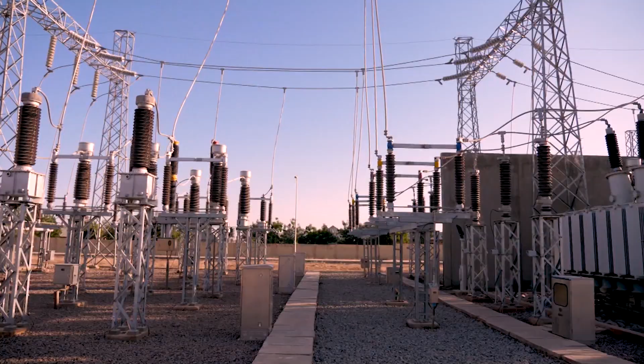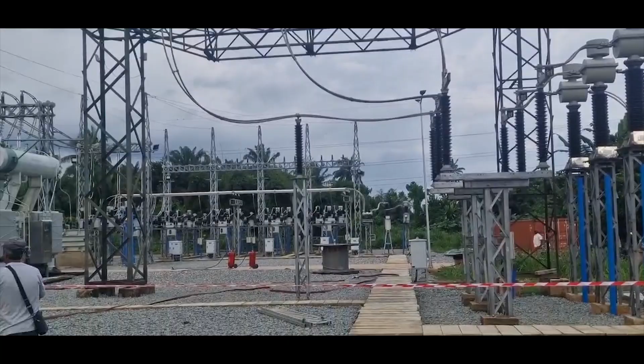In its usual quest to improve electricity transmission system capacity, the Transmission Company of Nigeria TCN has increased the bulk power evacuation capacity of the 132-33 kV Alaoji transmission substation in Abia State to 850 MVA. The feat was recorded after the management of TCN authorized the energizing of a newly installed 100 MVA power transformer in the substation.